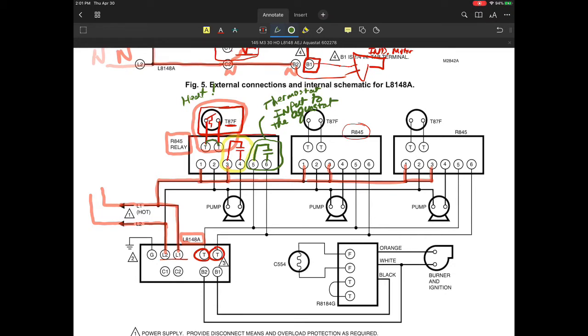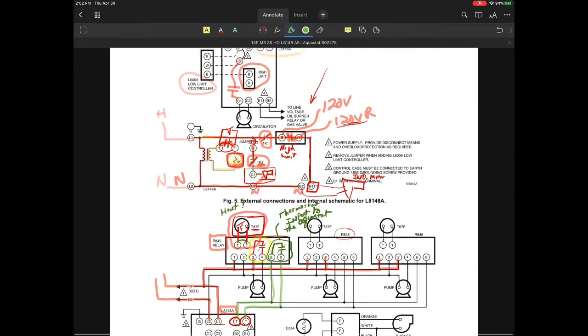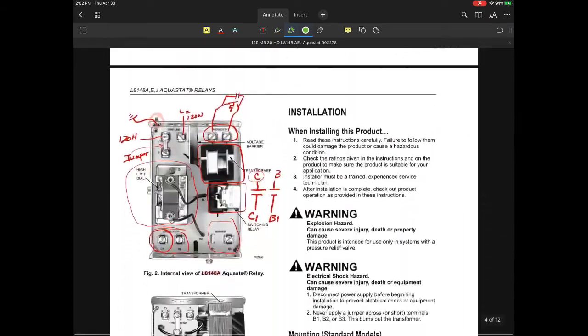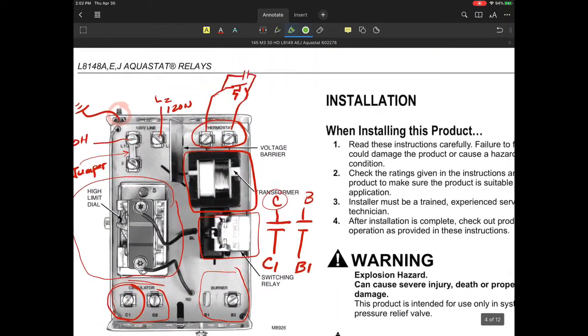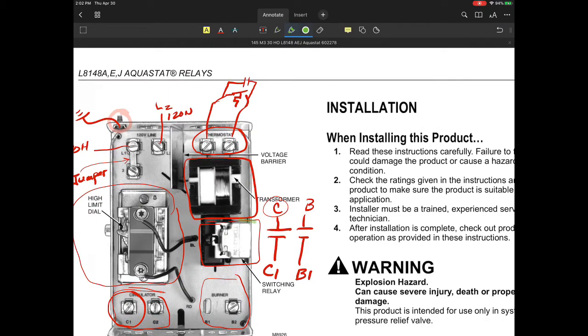So let's look at how this happens. So let's say this first one has a heating demand. So this one says we want heat. Yes, I want heat. This closes, we complete that circuit. So now when that closes, that means this will close simultaneously. When that happens, I'm going to switch to the highlighter, between the T, this one here and this one, it'll go through the contacts, come back out on here, and it'll complete the T to T circuit.